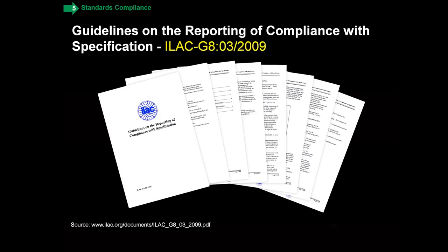Now we want to go back to the test point labeling challenge we looked at earlier. If it's way out of spec, we all know that's a fail; if it's way inside, that's a pass. The real question is: what do you do when the measurement uncertainty crosses the specification? That's really what ILAC G8 is all about. Look at the title — there's a link at the bottom, you can download it, it's free, and it's only about 10 pages long. Guidelines on the Reporting of Compliance with Specification.